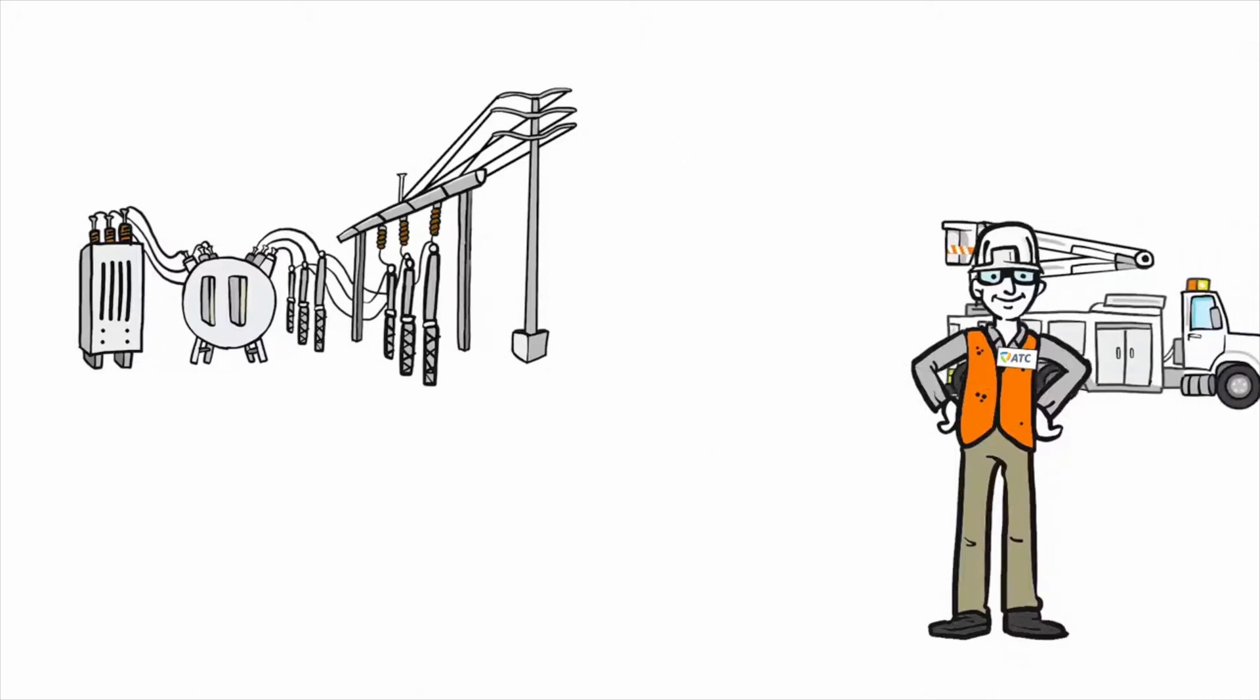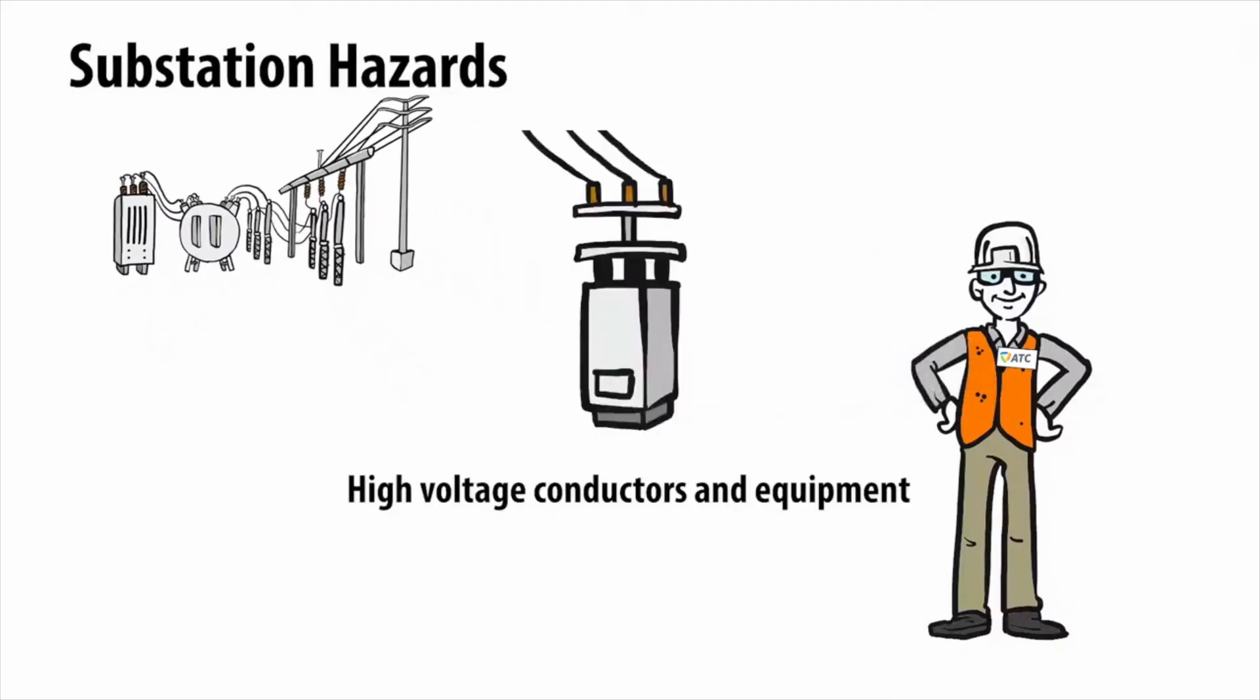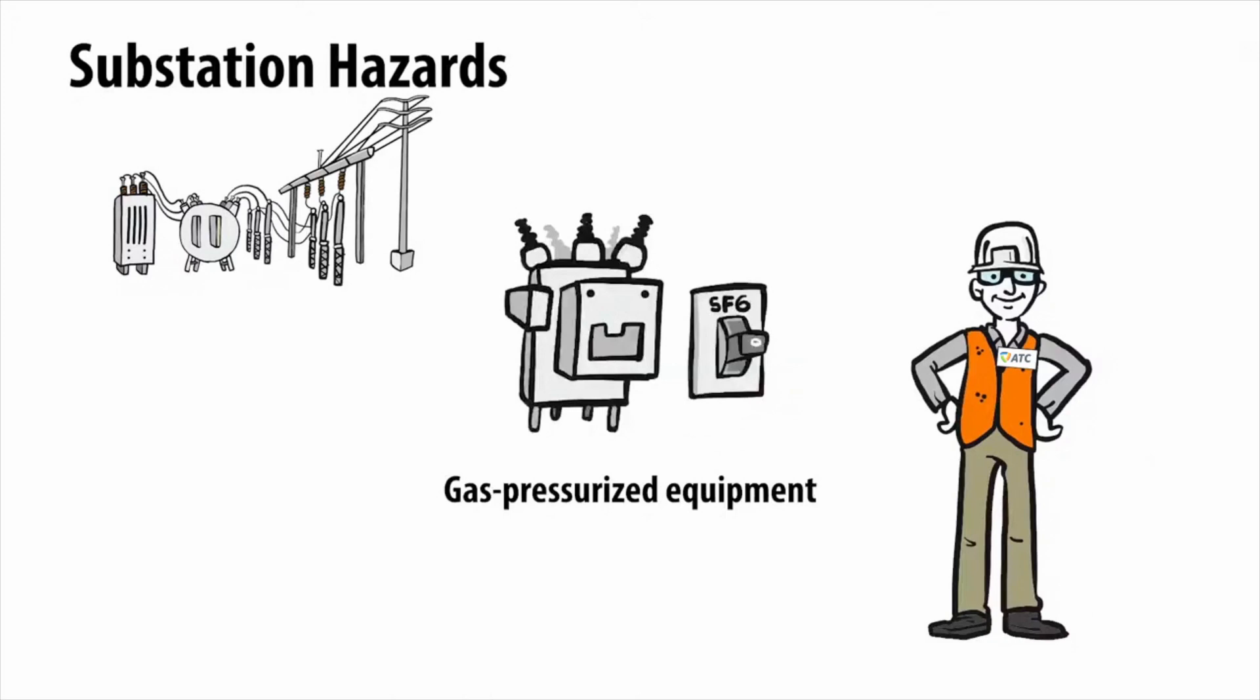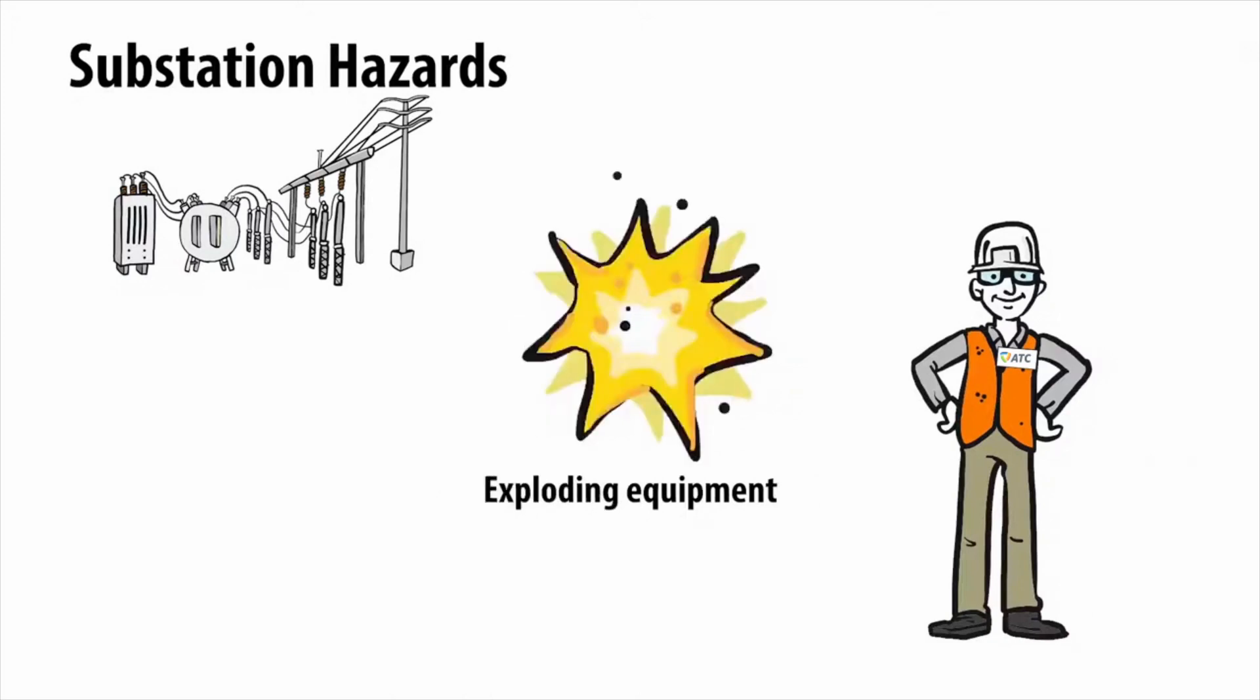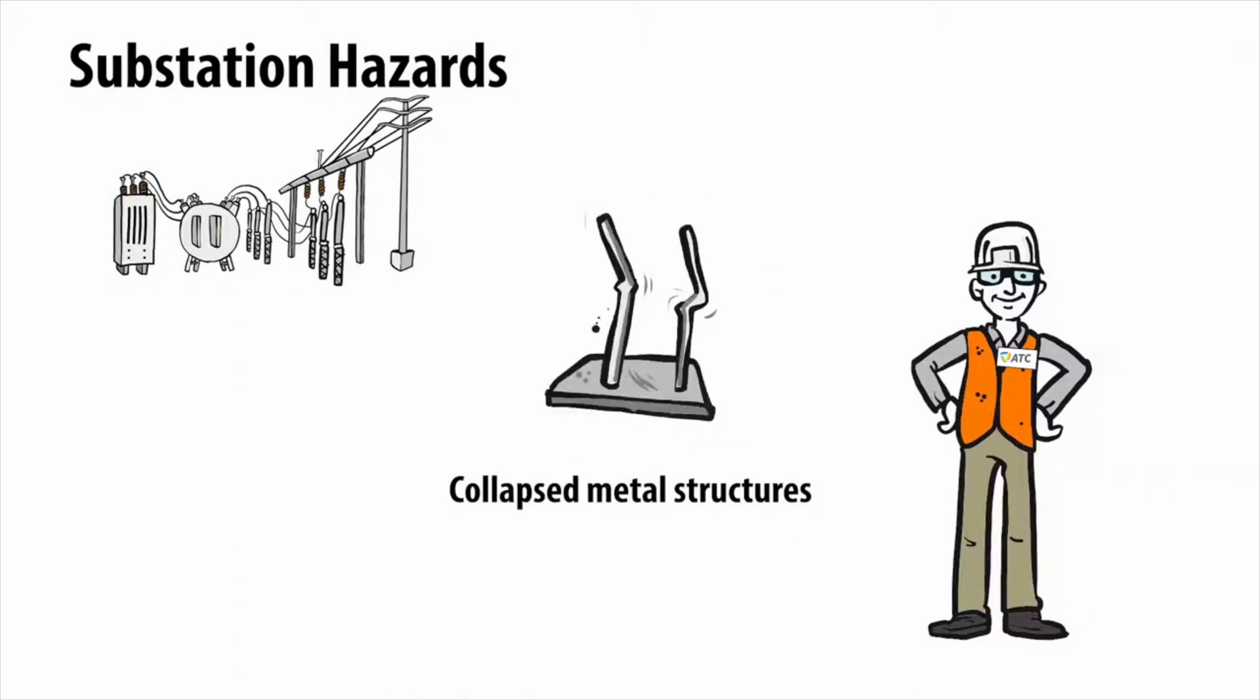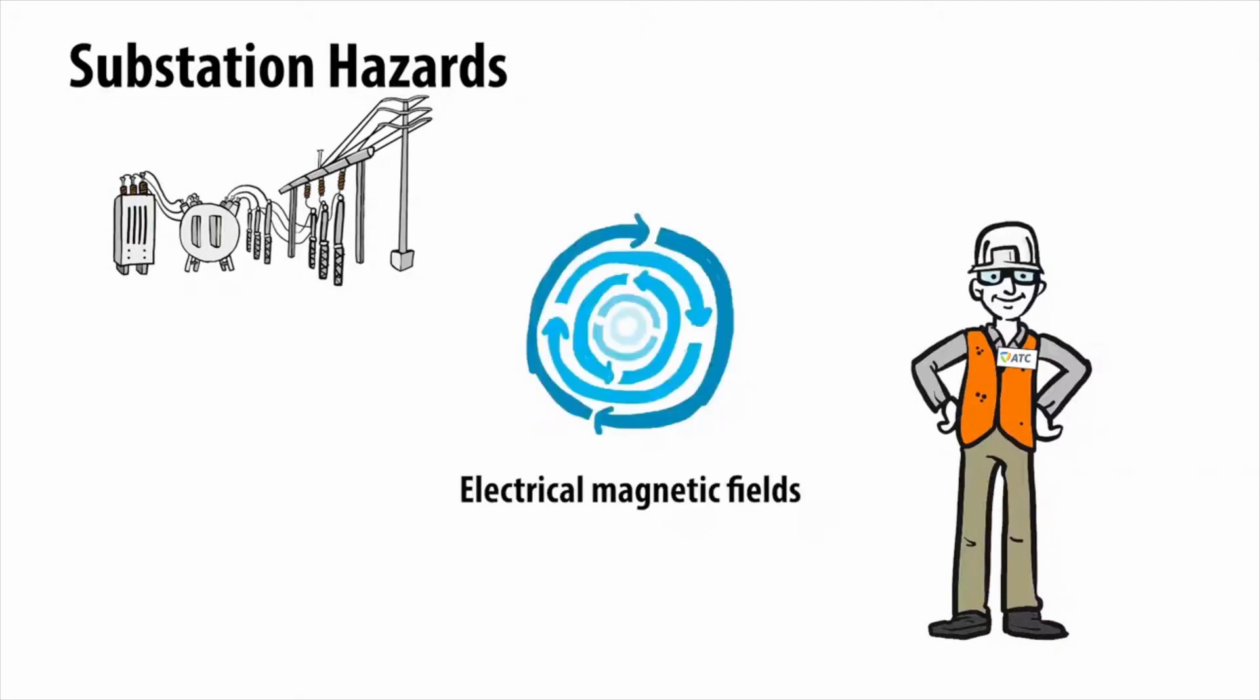Some hazards may be the result of mishap. Others are part of normal operations. Hazards include high-voltage electric conductors and equipment, oil-filled equipment that can ignite at 400 degrees Fahrenheit, gas-pressurized equipment, exploding equipment, toxic smoke, gases and chemicals, collapsed steel and aluminum framework, hot surfaces, and electrical magnetic fields.